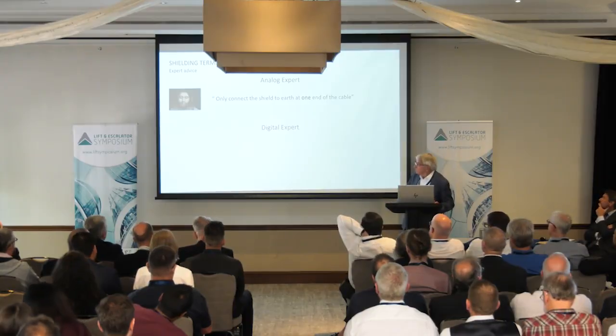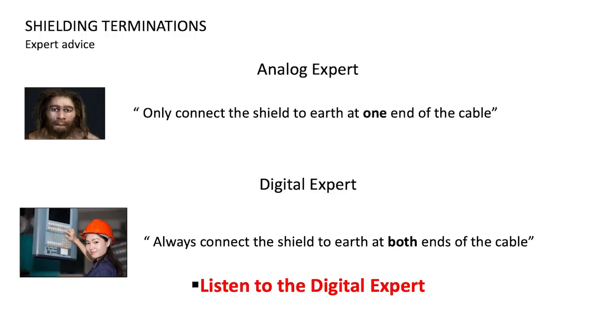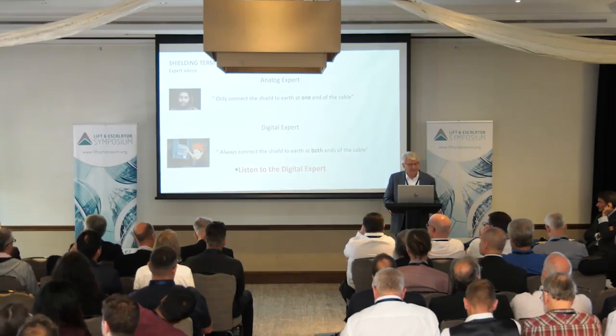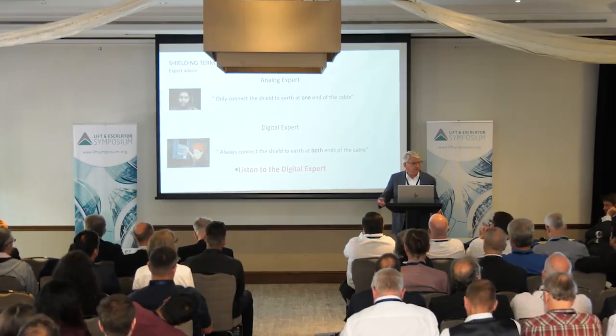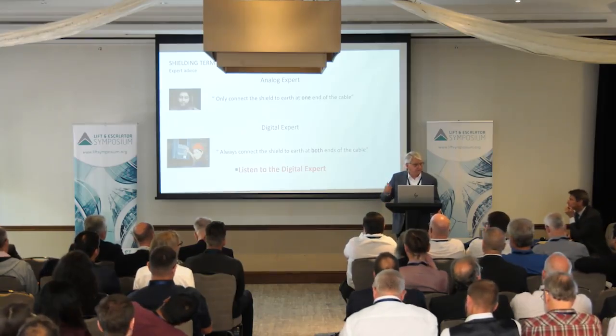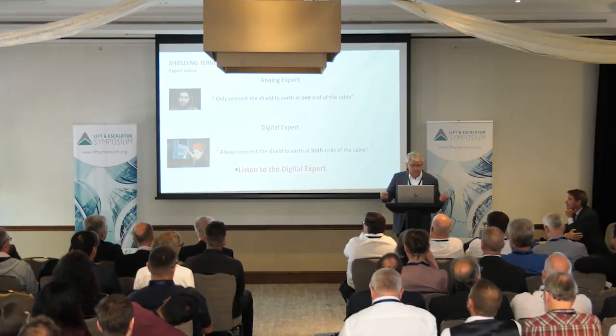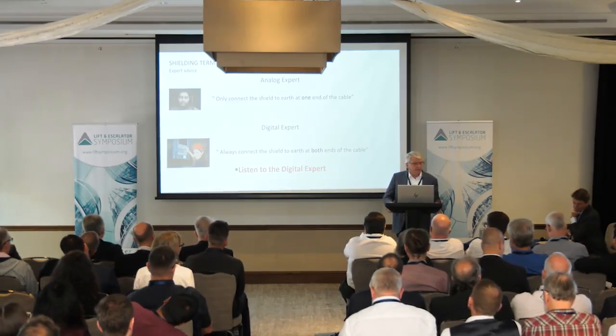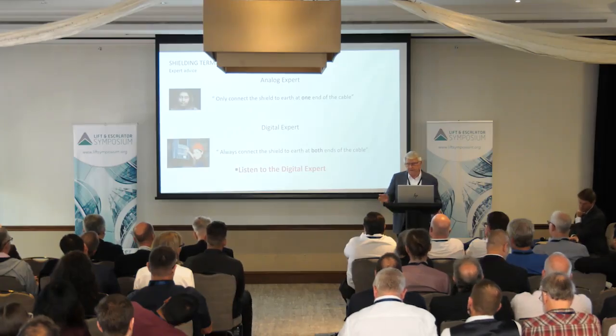A digital expert will tell you to always connect the shield at both ends, but a lot of people are still connecting them at one end. My advice is to listen to the digital expert, because unless you're dealing with an older system with a DC tachometer, you want to shield both ends. People say that if you shield both ends you get ground loops, and that's true in the analog world, but we're in the digital world now, and it's completely different.